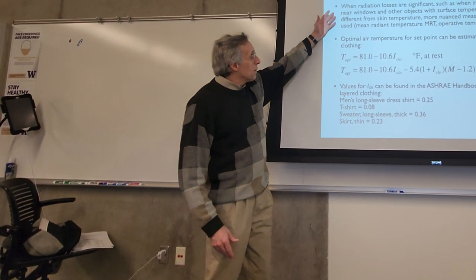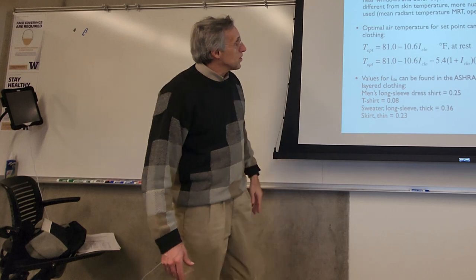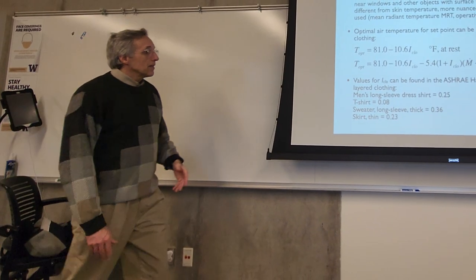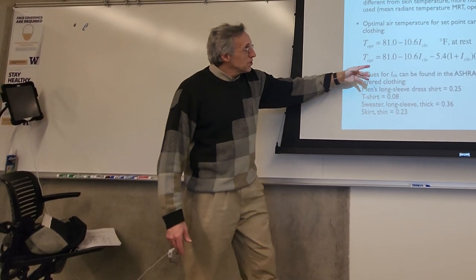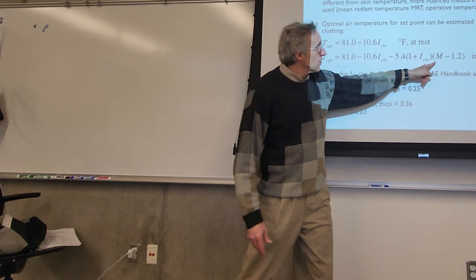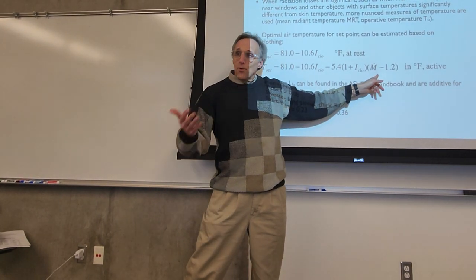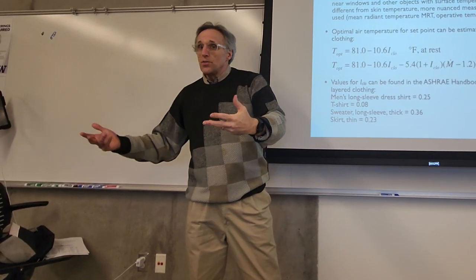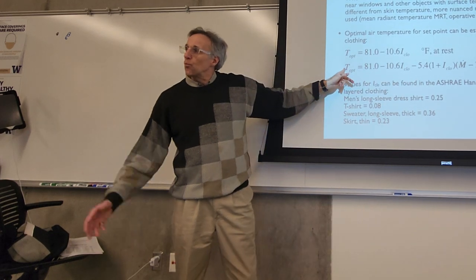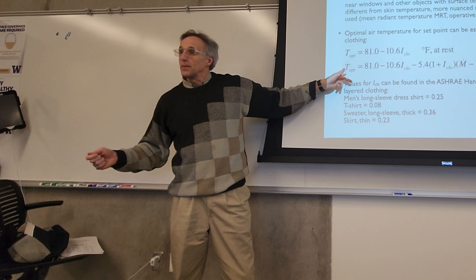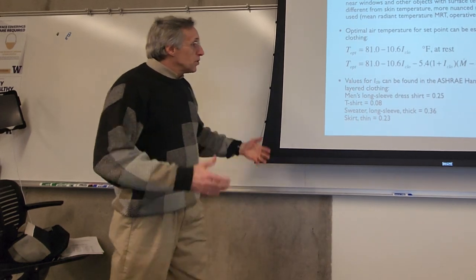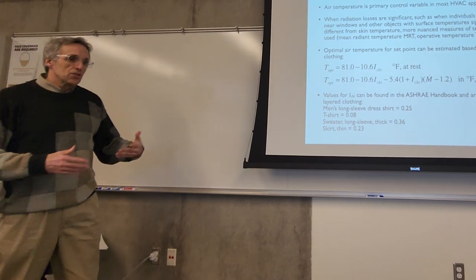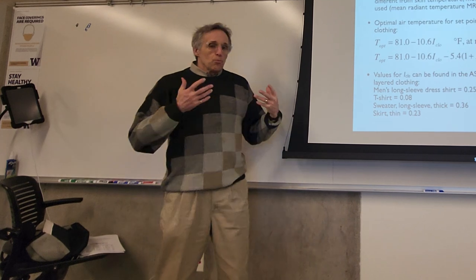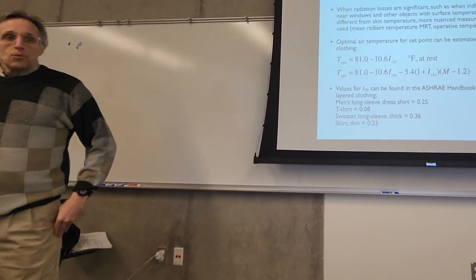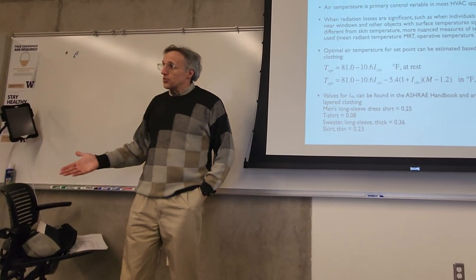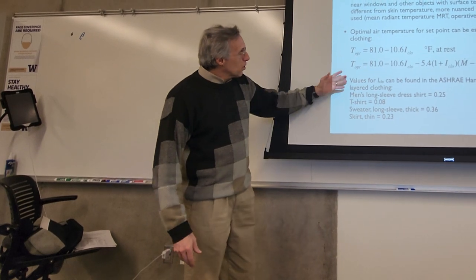But anyway, a number that I prefer using is the optimal air temperature based on our activity and our clothing. The second one here is actually my preferred one because it takes into account our ensemble of clothing, as well as our metabolic activity. So you can take a person, figure out their body area, what they are doing, how much energy they're outputting, and what they are wearing, and then you can calculate the ideal temperature to make that person comfortable. That's what that formula will give you. And so you may be trying to cool or condition a space where you're doing some kind of strange activity. Maybe this is a room where all you do is really intense exercise, so you want to condition it to maybe 40, 45 degrees. Who knows? But you can figure out what it is and design your HVAC system accordingly.